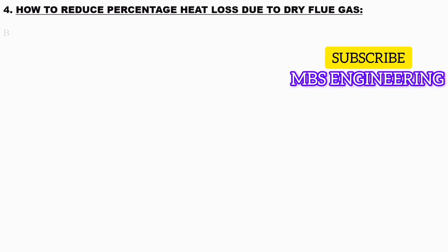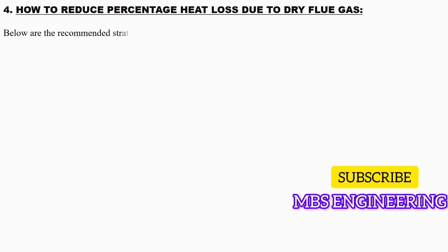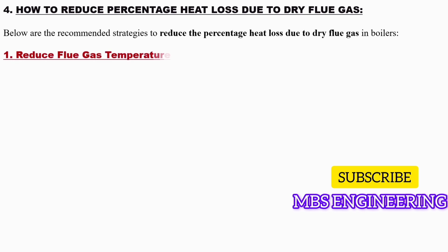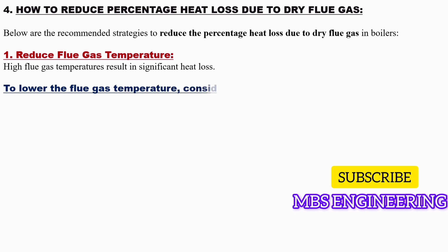Next, we will learn and understand how to reduce percentage heat loss due to dry flue gas. Below are the recommended strategies to reduce the percentage heat loss due to dry flue gas in boilers. The first recommendation is reduce flue gas temperature. High flue gas temperatures result in significant heat loss. To lower the flue gas temperature, consider the following measures.